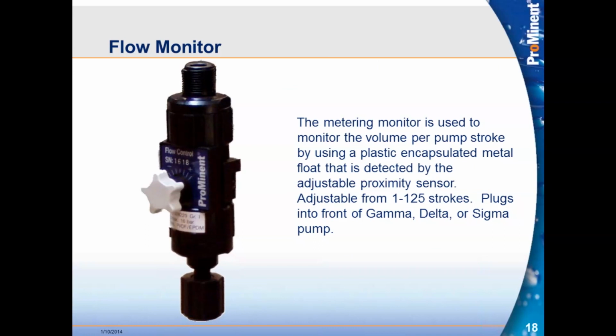We also offer flow monitors. Metering monitor is what I've always known it as. It's labeled flow control, and personally I don't like that label. We're not controlling the amount of flow with that, so I think that's a little misleading personally. I like to call it a metering monitor. That's what I knew them as when I started, and still refer to it as that. So if you're ever talking to me for any reason and I say metering monitor, this is the device I'm talking about.